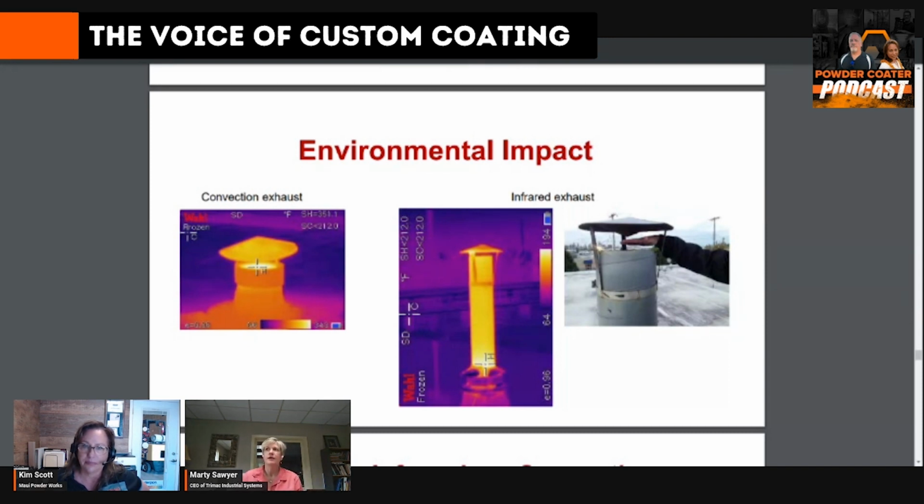And you think about, God, all that heat you're paying for, you're just paying for it and just throwing it away. And you're going to do it constantly, because that's the code. So the center one is the catalytic stack. And you can see, obviously, it's much cooler. It's at the very bottom where it's heated up a little bit, because there's obviously some extra metal there. So it's heated up, you're under 200 degrees there. The other one's at 350.